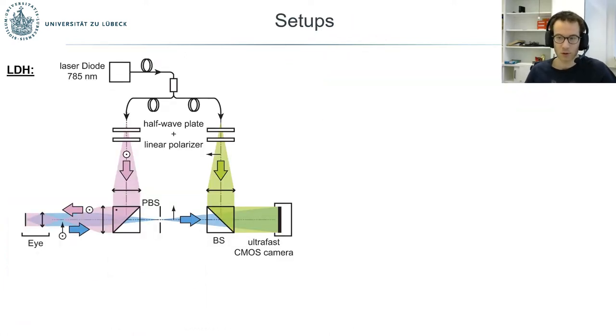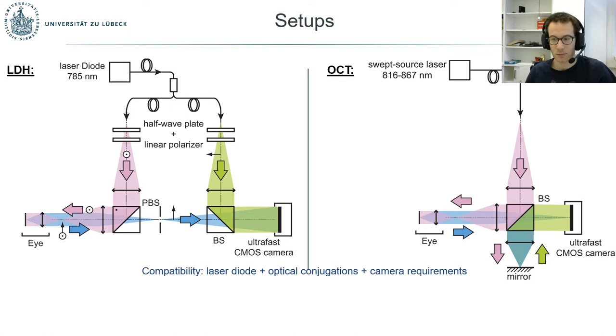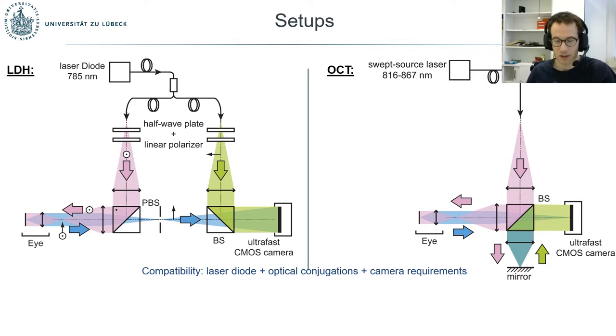The setups for these two imaging techniques are as follows: on the left is LDH and on the right is OCT, and you can see that there are many similarities between the two — they are quasi-identical, which makes them compatible. They both use a laser diode and the same optical conjugations, so the light is focused in the front focal plane of the eye, and the light backscattered is combined with a reference beam onto an ultra-fast camera. The requirements in terms of camera frame rates are also similar, about 60 kHz.